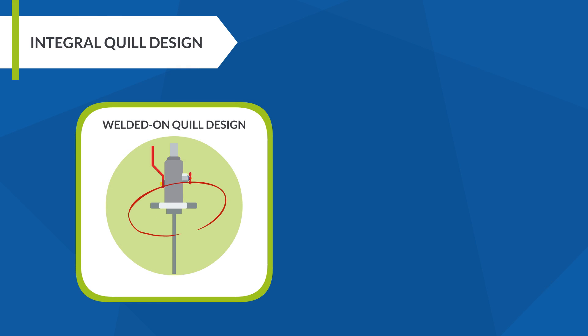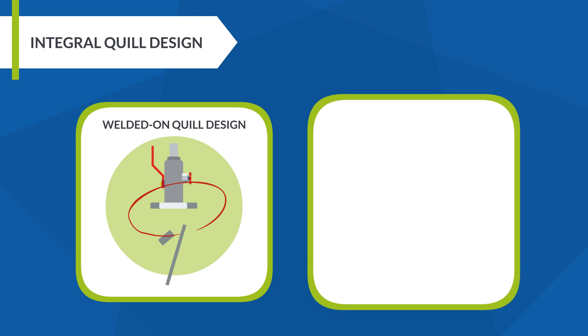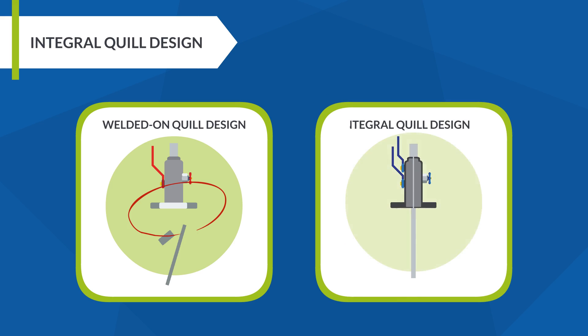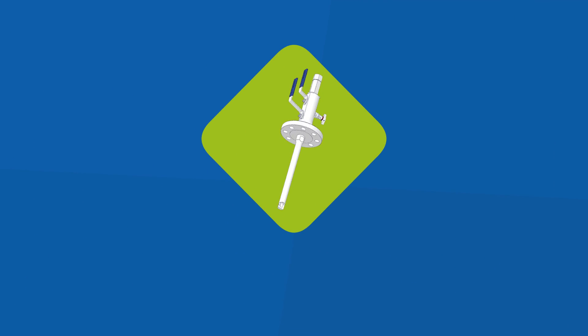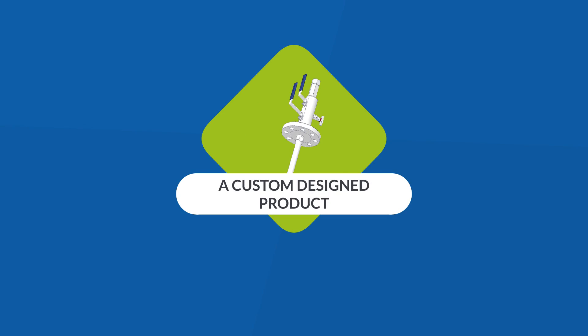Integral quill design. These are injection quills available with a welded-on design which are prone to fatigue fracture caused by vibration. To increase safety, make sure that the injection quill you use is made of one-piece integral design.